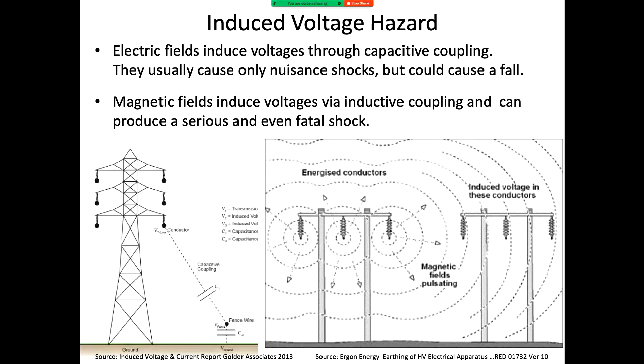The more dangerous element is induced voltage from magnetic coupling. Say you've got two long lines, one energised and one de-energised. You might think the de-energised one isn't a problem, but you can actually get induced currents and induced voltages on that line. Currents induce voltages, and if you close a circuit, you produce currents. That's the induced voltage hazard.